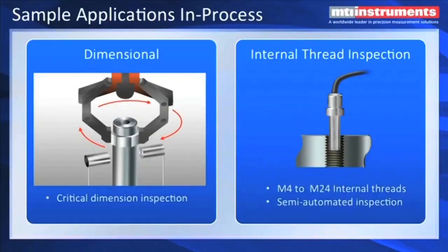And recently we've introduced a thread inspection system where we can, using an internal thread inspection probe that's got a ring around it, look at a 360-degree displacement measurement as it's inserted into the threads, and we can generate a profile as you insert that probe down in the threads to make sure the threads are all there. It's the correct pitch diameter, that the threads don't stop short of where you intended.